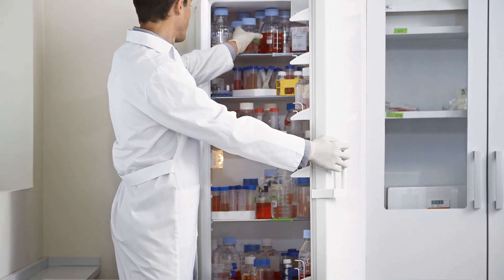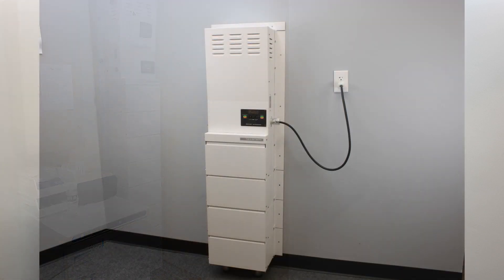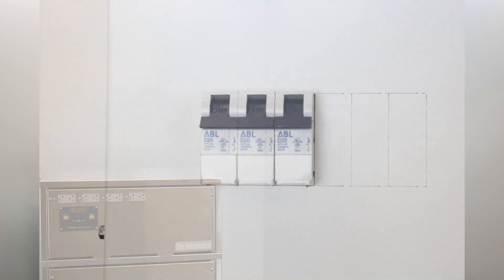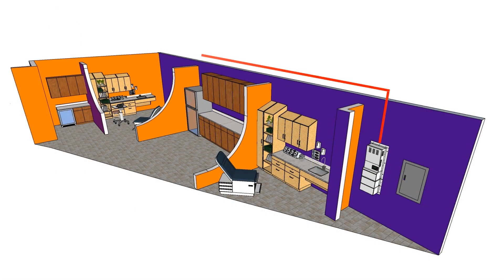This led to our next product, the Silent Sentry. The Silent Sentry is a tall slender system. It mounts to the wall and uses virtually no floor space. This can be configured as a hardwire system or a standalone plug and play system. The standalone plug and play system plugs directly into a regular wall outlet and the appliance is plugged directly into the side of the power system. When configured as a hardwire system it incorporates branch circuit breakers that power circuits throughout a medical building from one central location.